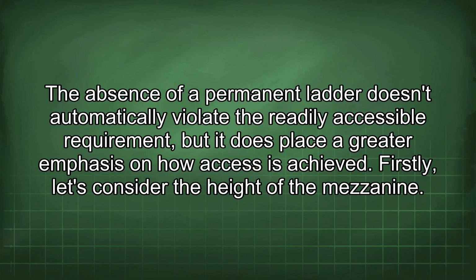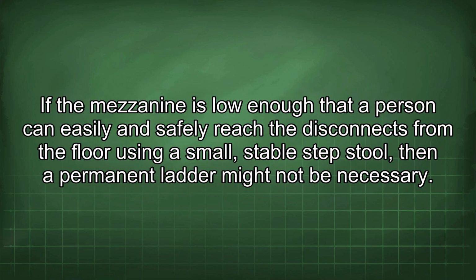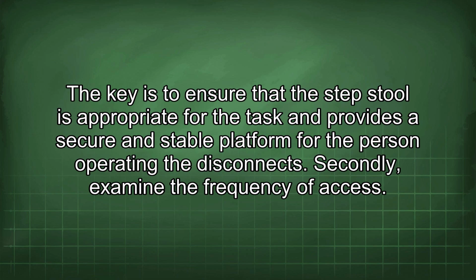Firstly, let's consider the height of the mezzanine. If it's low enough that a person can easily and safely reach the disconnects from the floor using a small, stable step stool, then a permanent ladder might not be necessary. The key is to ensure the step stool is appropriate for the task and provides a secure, stable platform for the person operating the disconnect.